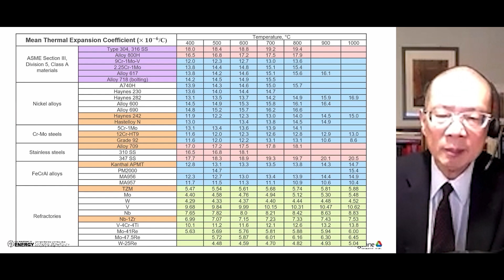The figure on the left was based on using stainless steel and alloy 617 and performing this bar calculation. And then we plot out the follow-up factor and the strain range. The figure on the right corresponds to replacing alloy 617 by moly. We basically do the simulation using different properties, but with the same thermal cycle conditions. And then the results show that the strain range as well as the elastic follow-up factor are significantly improved or enlarged. So within the design envelope, we can find design points that can allow us to have a larger strain range.